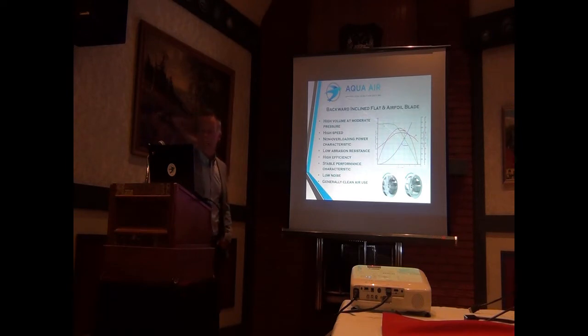Backward inclined flat and airfoil blade. We're showing the one curve here because they're very similar. Like I said, the only real difference is the shape of the front edge of the blade, and the efficiencies are very similar. They have higher volume at moderate pressures, higher speeds, and non-overloading power characteristics. How does that compare to that forward curve fan? If you look here at that green line, it goes up, gets to a peak, and curves down. So you also don't want to be at the top of the curve. You want to follow that same basic rule of 90% of your static pressure and stay on the right-hand side. But if it happens to go over, it won't overspeed or speed itself up. It's almost self-regulating. It won't go over the design of what it can do. It just won't push any more air or build any more static pressure.